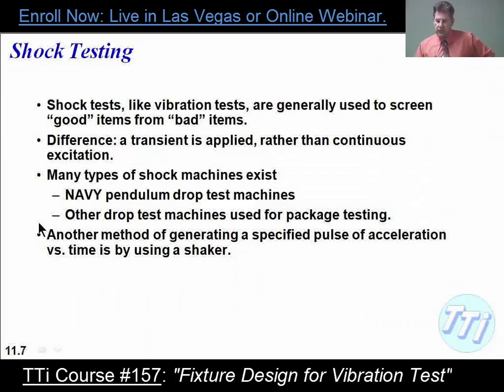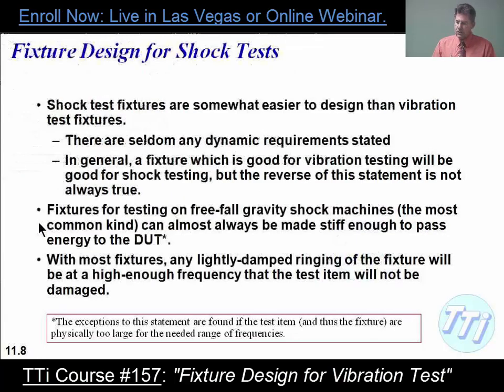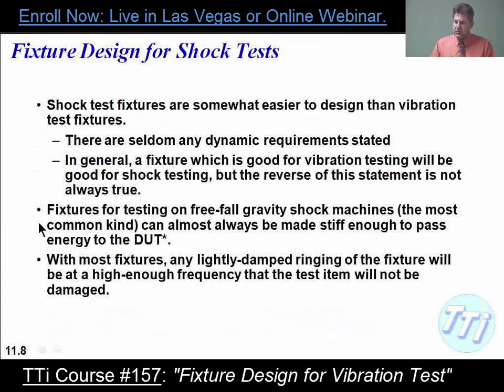Now, shock fixtures. The goal of shock testing is to screen good things from bad things. The big difference is that you apply a single event or transient rather than continuous excitation. The whole idea with a shock test machine is that you store energy and deliver it in a controlled way — you can use gravity, compressed springs, or a shaker using electrodynamic force. Shock test fixtures are a little easier to design than random vibration fixtures, often because dynamic requirements aren't specified. A fixture that works for vibration will generally be good for shock testing, but a shock fixture may not be good for vibration testing.